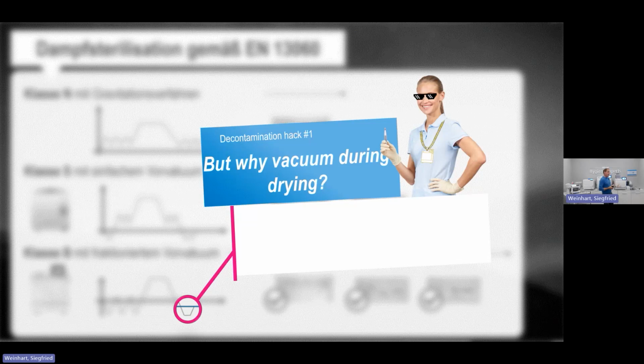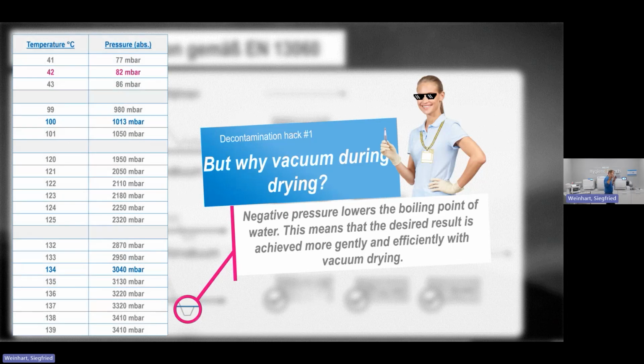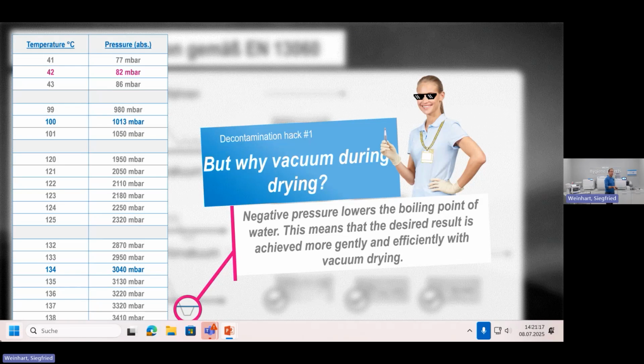And one of the things with vacuum autoclaves that we look at is obviously the time that they take, purely because they're trying to suck air out. They don't just suck the air out all in one go. It's a process of pulses to draw that air out. Now, the reason they do vacuum drying is that it's also that negative pressure. It lowers the boiling point, so you get a more desired result, gently and more efficiently, during the vacuum drying. So it helps to ensure that those instruments come out completely dry.